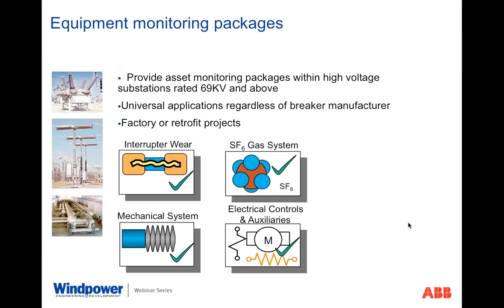As part of this, ABB has been designing equipment monitoring packages since the mid-1990s. These monitoring packages consist of electronic devices that are built in the U.S. specifically for high voltage breaker applications, primarily SF6 gas breakers rated 69 kV and above. Our monitoring packages range from a standard SF6 gas monitor to a full-featured device that supports all of the four areas of monitoring that you see here. Our universal monitors can be used for any SF6 breaker, regardless of manufacturer, even supplying our monitoring package to other OEM manufacturers to allow the end users the ability to receive monitoring packages on all their factory purchased breakers.